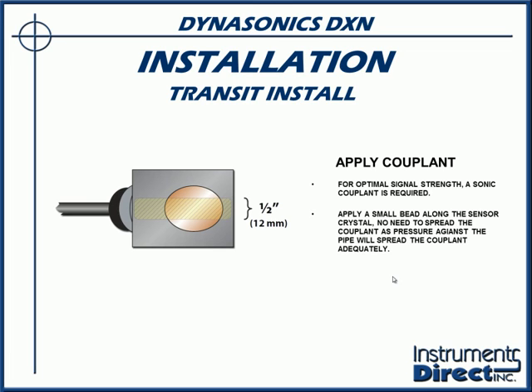We need to put some acoustic couplant on the outside of the transducer. A very popular question, how much do I put on my transducers? Rule of thumb is toothpaste on a toothbrush. The sensor is flat, the pipe is round. We need an acoustic pathway to send our sound beam through.